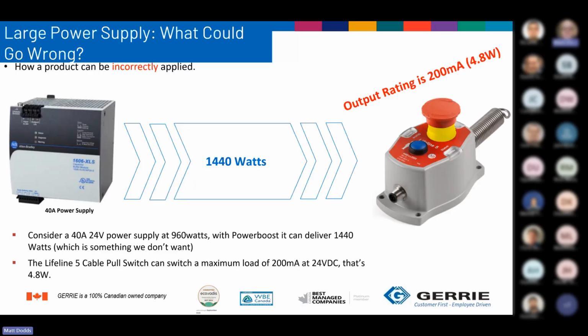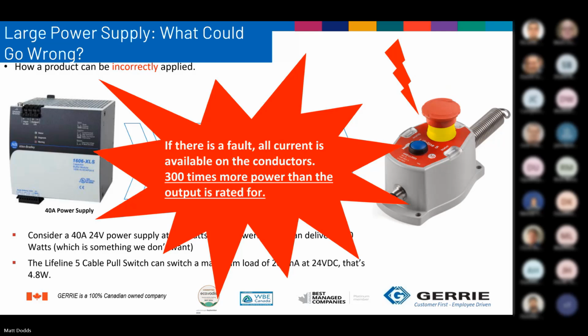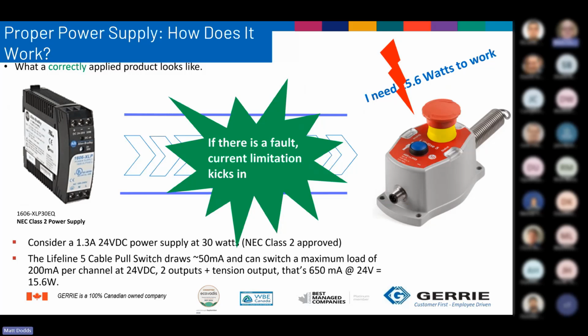So what happens? The device is rated 200 milliamps, 4.8 watts. I have a 40 amp power supply providing 1,440 watts. If I short the output, I just made a really expensive fuse. It's like 300 times more power than the output's rated for, so that's a problem. If I put in the correct size power supply and there's a fault, current limitation kicks in and will protect those outputs from shorting. So very important. Or again, you can use electronic circuit protectors.